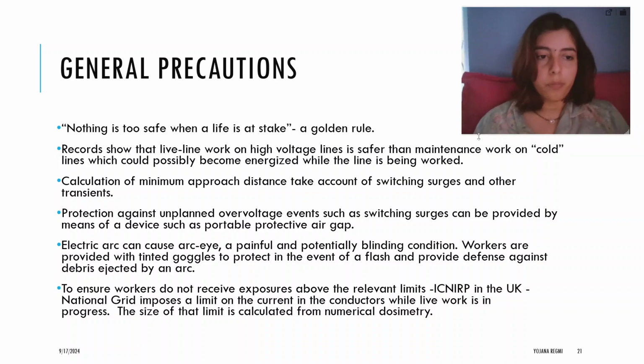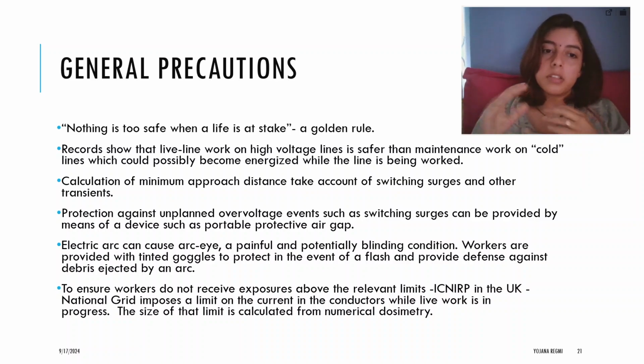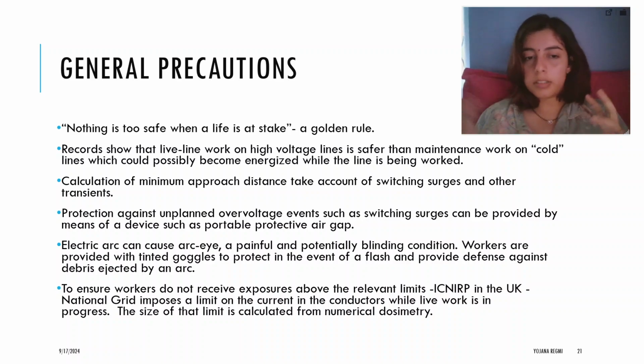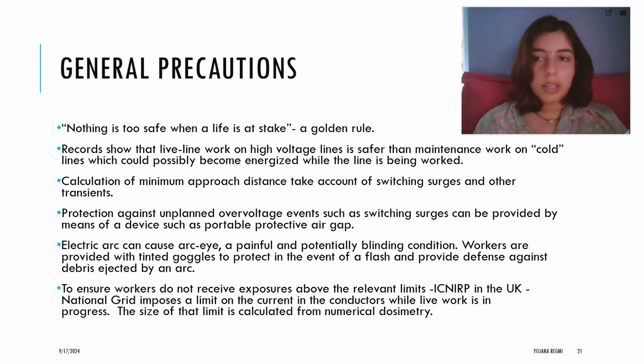The calculation of minimum approach distance takes account of switching surges and other transients, so you have to maintain a distance when using the hot stick method, based on the voltage. Protection against unplanned overvoltage events such as switching surges can be provided by devices such as a portable protective air gap. I could explain this further, but I don't think I have the time or the slides needed to explain it.